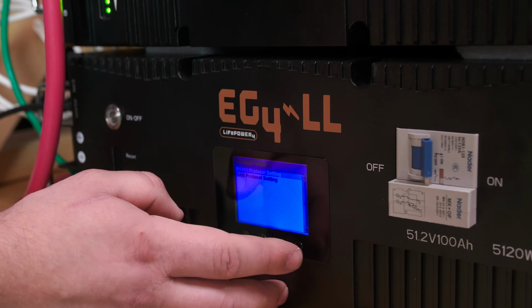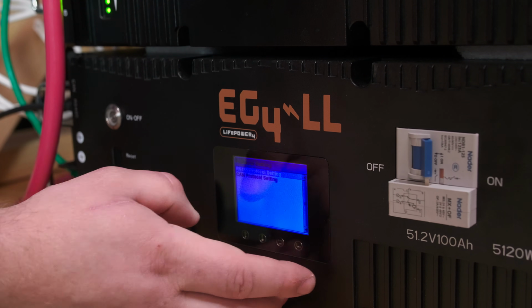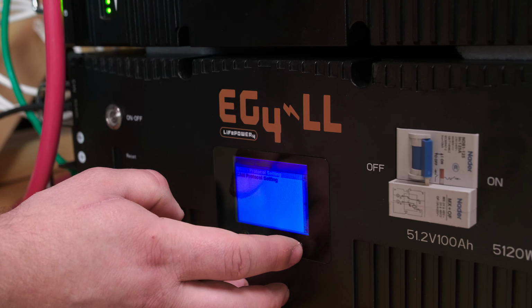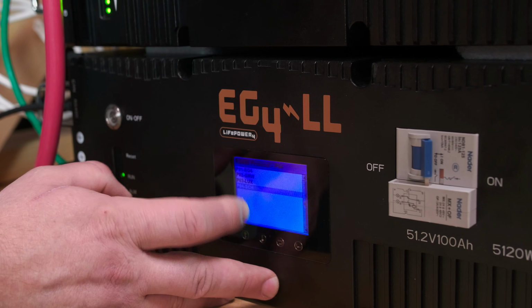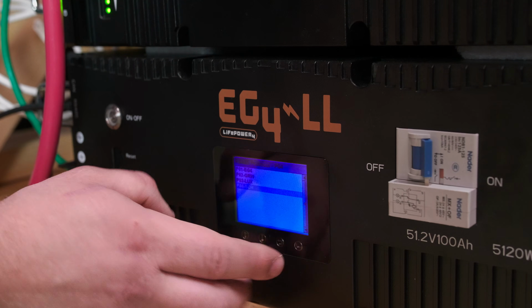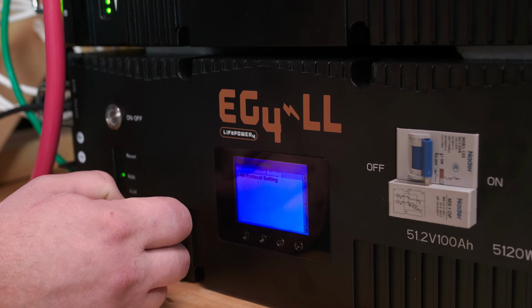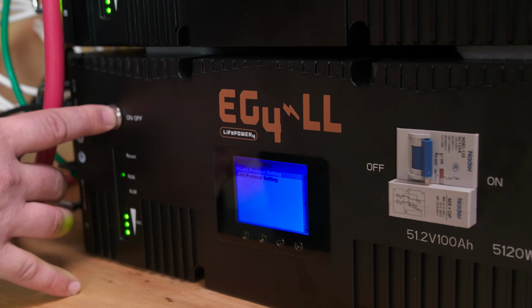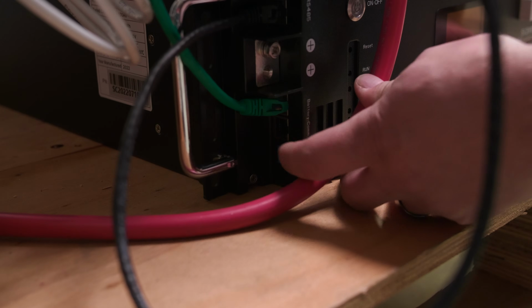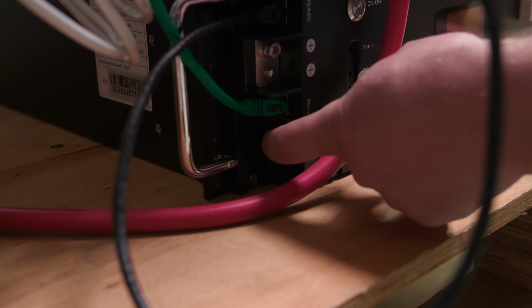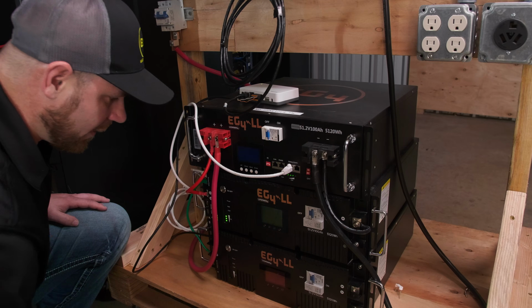Here you've got the protocol list. Go to RS-485, and Schneider is going to be at the bottom right here. Hit enter, and then turn your BMS off. Set your dip switch to 1, which is going to be the top dip switch, and turn it back on.